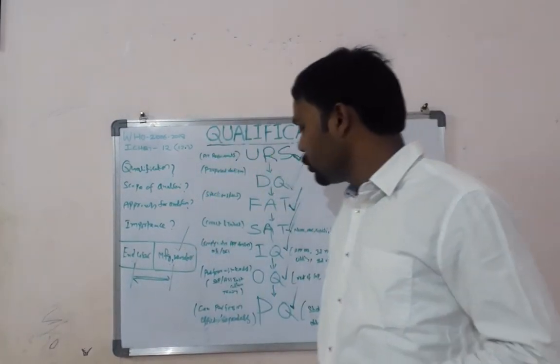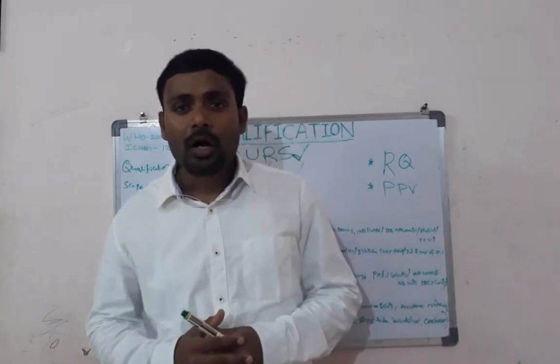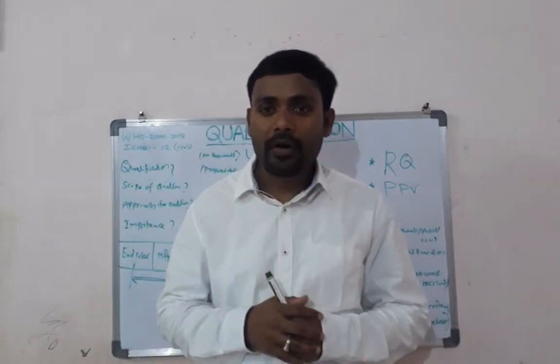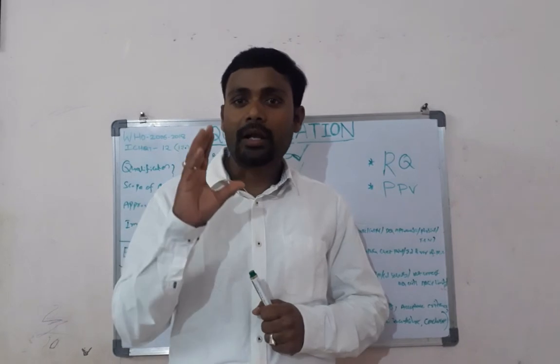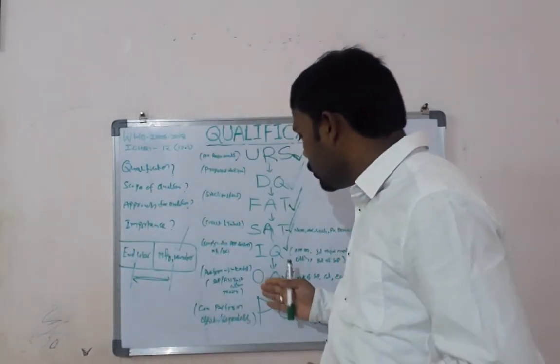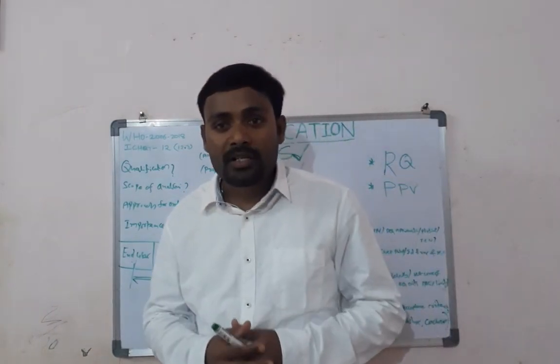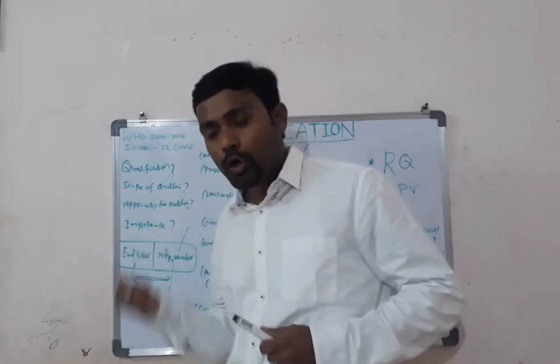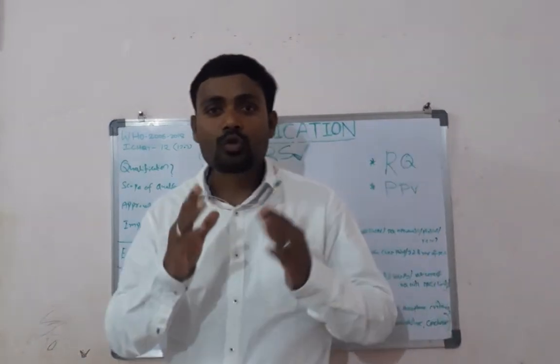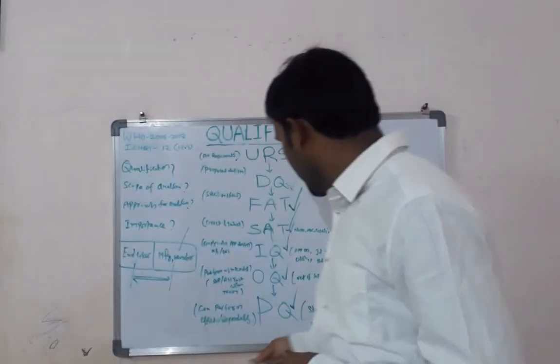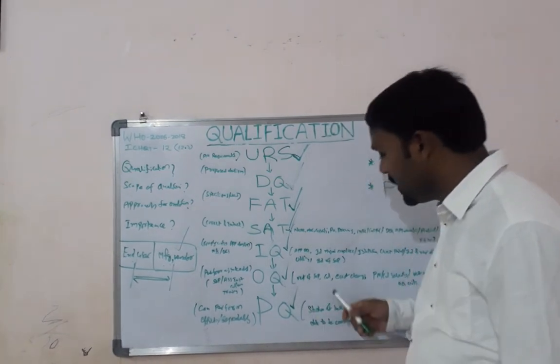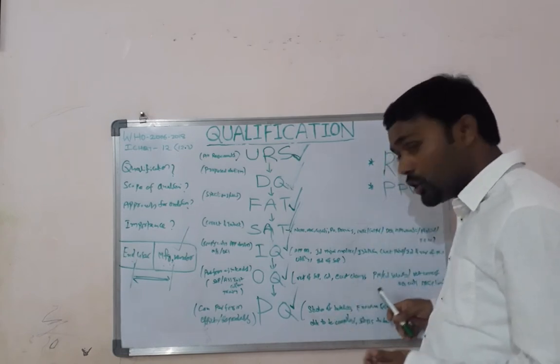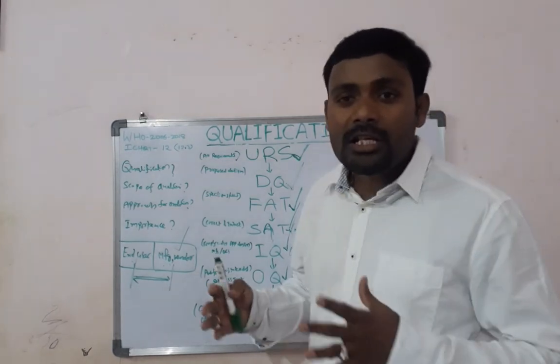Operational Qualification (OQ) is a documented verification that an equipment or system as installed or modified can perform over its anticipated operating ranges. Before starting OQ, SOPs for equipment operation, maintenance, and calibration must be in place, all associated instruments must be in a calibrated state, and relevant personnel must be trained. The OQ report covers SOP verification, calibration, cleaning procedures, preventive maintenance planning, and outcomes within specified limits.